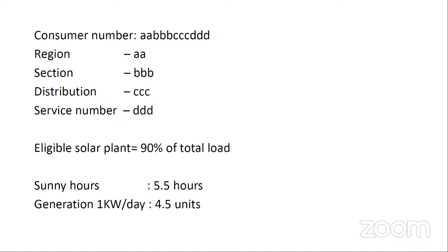Next is unit and assessment amount tabulation. To arrive at the capacity of the plant, you need to take the average of the last 10 months or 1 year of data, because in winter the requirement will be less and in summer it will be more. You should not design a system based only on summer or only on winter requirements.